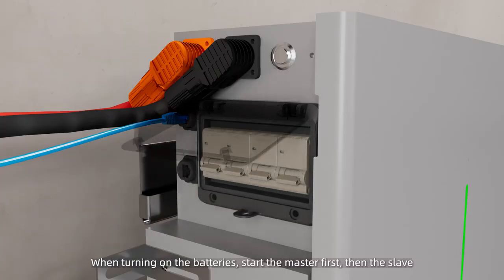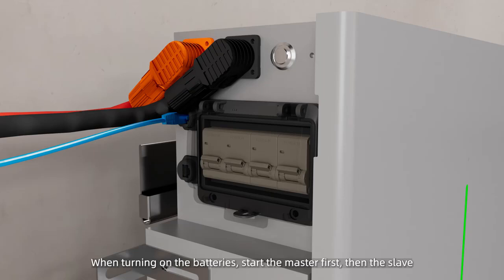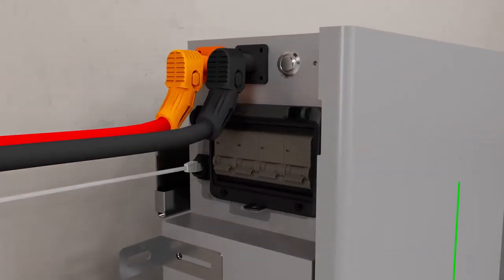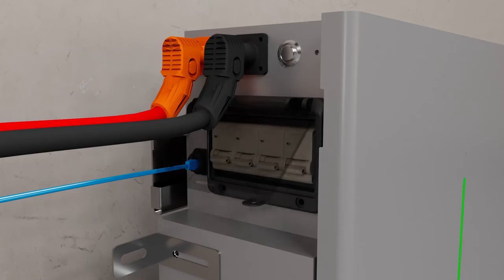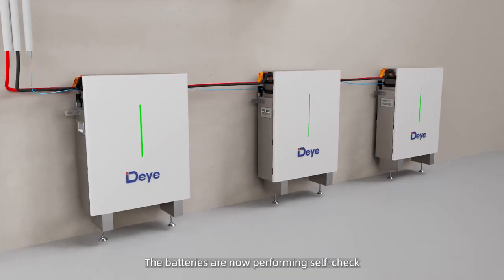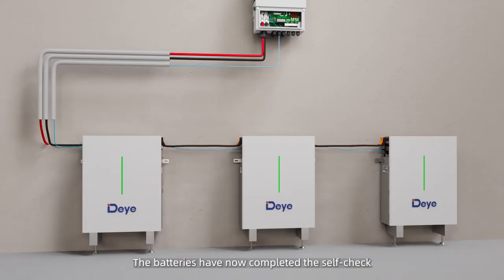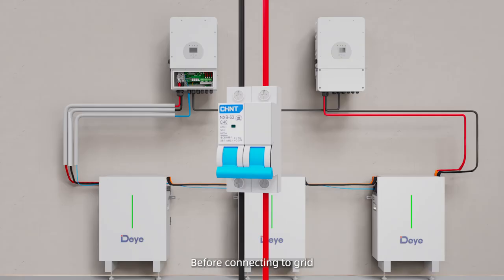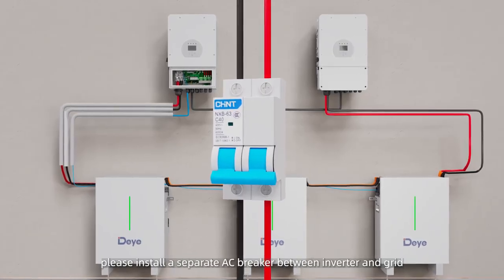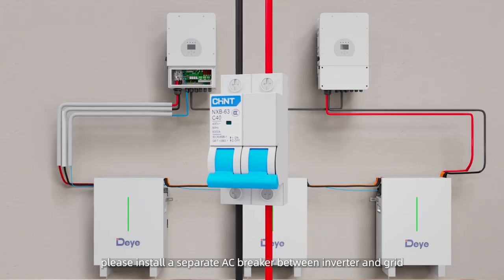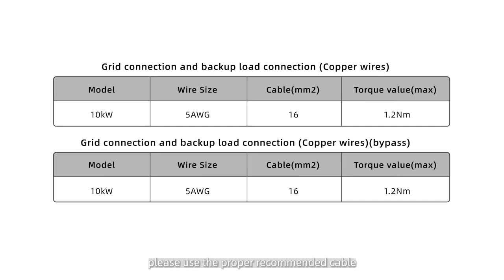When turning on the batteries, start the master first, then the slave. The batteries are now performing a self-check. The batteries have now completed the self-check. AC side connection. Before connecting to grid, please install a separate AC breaker between inverter and grid. It is also recommended to install an AC breaker between backup load and inverter. Please use the proper recommended cable.